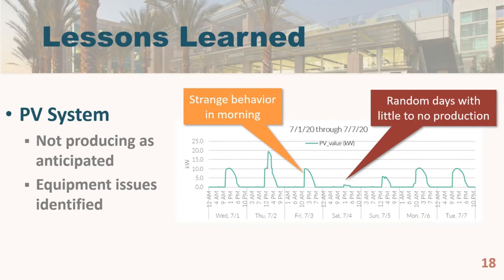They identified some programming issues and some faulty modules, and those will be fixed, and the project will be back on track for zero net energy. One reason I highly recommend having your own PV meter is that even if your project has third-party monitoring, our experience is that we're the ones who tend to tell them something's wrong with the PV system. I'm not sure why, but third-party monitoring systems and contractors don't usually identify these issues.